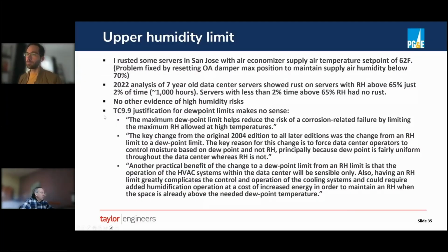The justification that ASHRAE TC9.9 has for the dew point limit doesn't make any sense to me, at least. In their guideline, it says the maximum dew point limit helps reduce the risk of a corrosion-related failure by limiting the maximum RH. And of course, if your concern is RH, you don't necessarily need to control the dew point. You need to control the RH. They go on to say that the key change from the 2004 edition to all the later ones was the change from an RH limit to a dew point. The reason is to force operators to control moisture based on dew point and not RH, because dew point is fairly uniform throughout the data center, whereas RH is not.